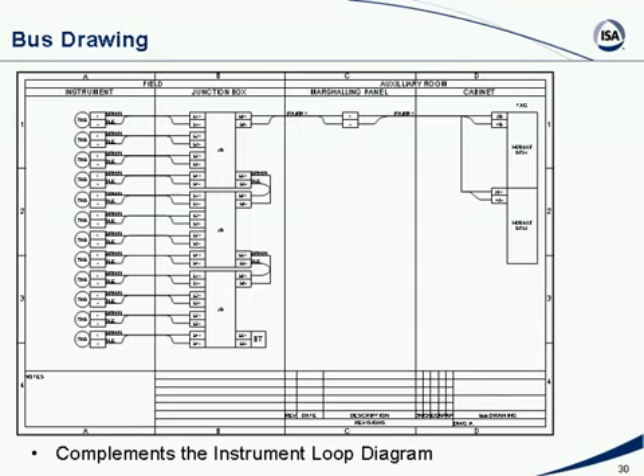For traditional 4 to 20 milliamp wiring, we used to have an instrument loop diagram for every loop or measurement point. With Fieldbus, this gets replaced by a segment drawing or bus drawing. One drawing now shows all the devices on the bus, maybe 16 or 8 or 12, whatever you have. This is important because if I'm touching one device, I want to know what other devices are on the same bus, so the technician knows how careful they have to be, since disconnecting this wire might affect 16 devices, not just one.